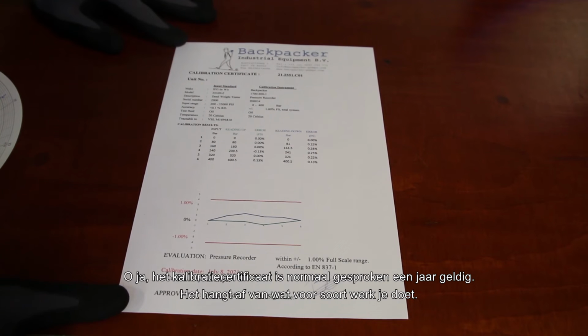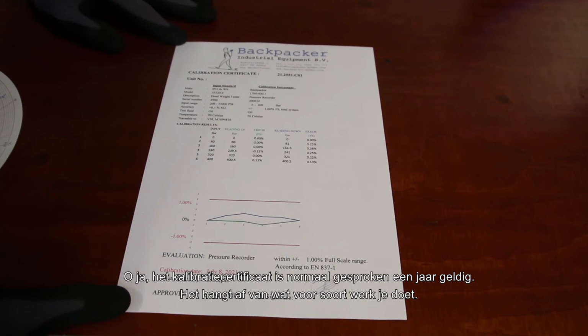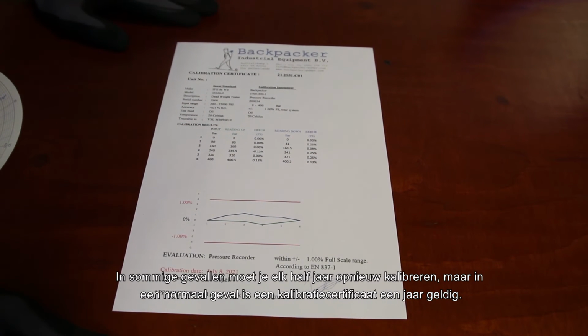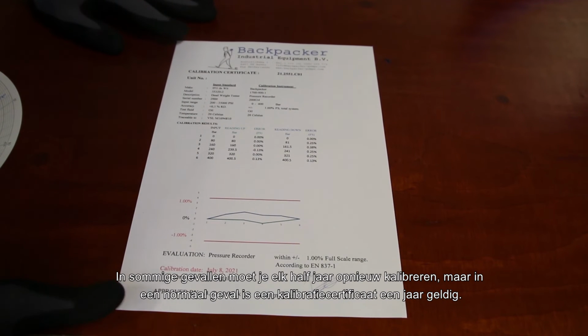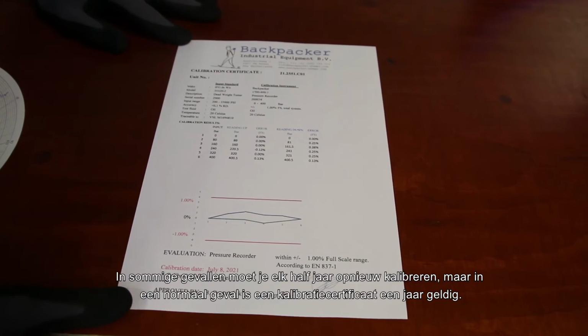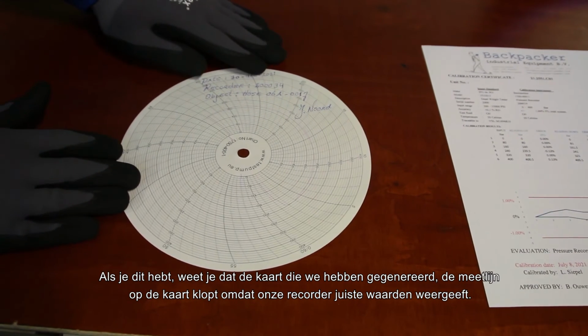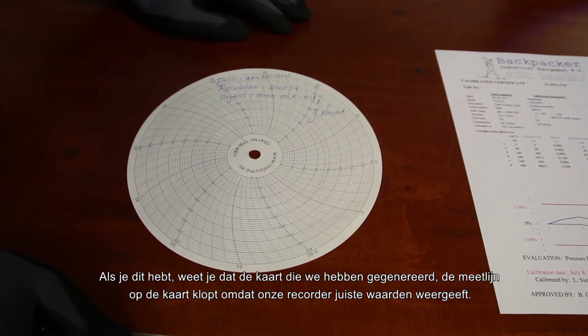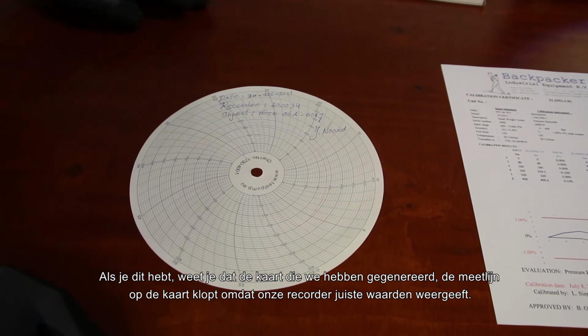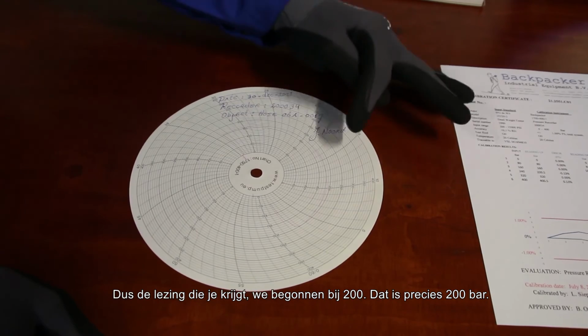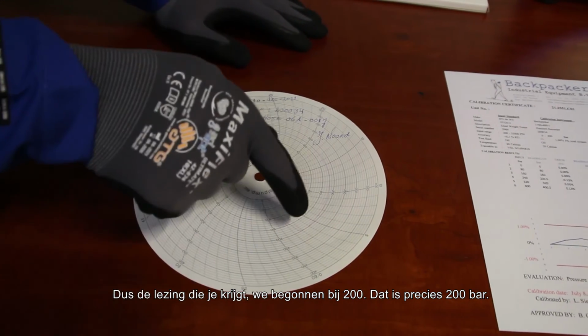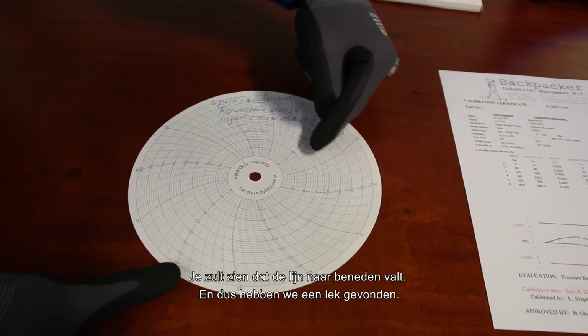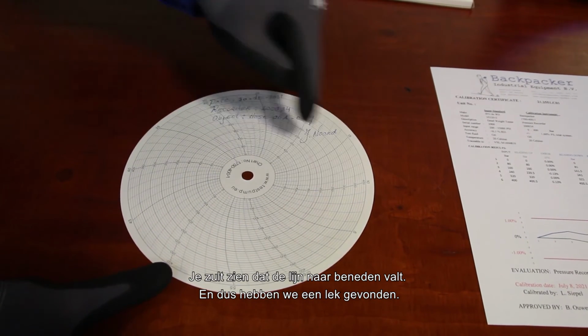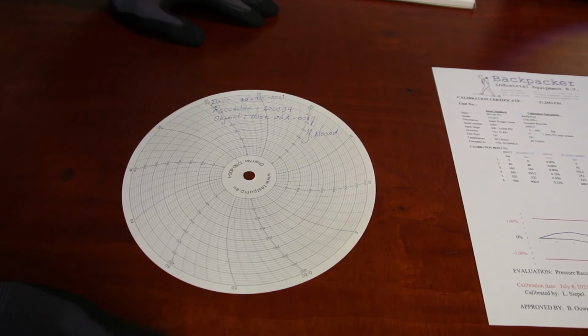Oh yeah, the calibration certificate normally is valid for a year. It depends on what kind of job you're running. In some cases you need to recalibrate each half year, but in normal instances a calibration certificate is valid for a year. Having this, you know that the reading on the chart we generated is exact, because our recorder is giving exact numbers. So the reading you get, we started at 200, that is exactly 200 bar. You'll see the line fall down, and so we have determined a leak.